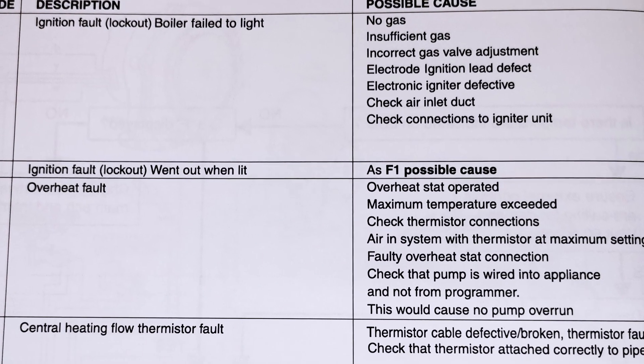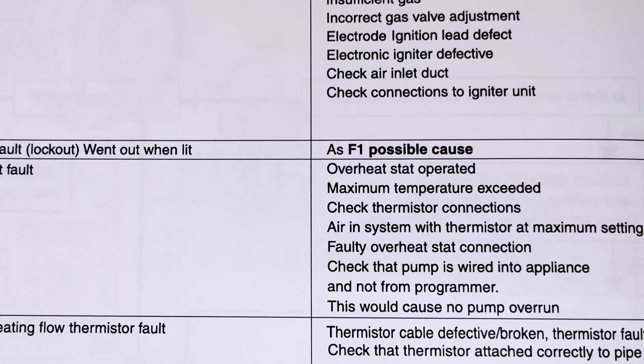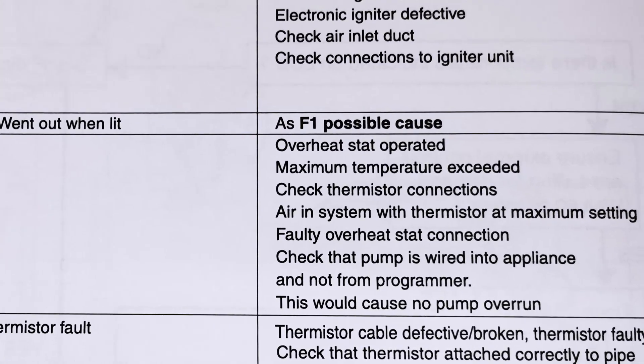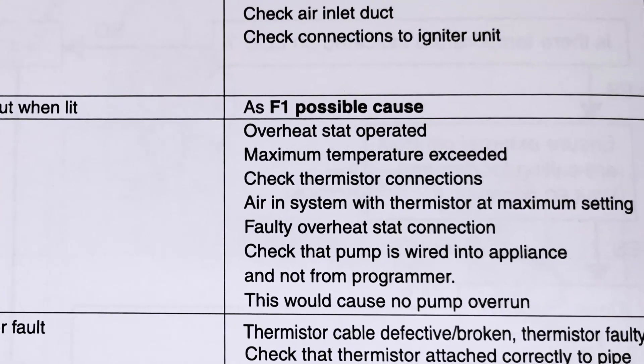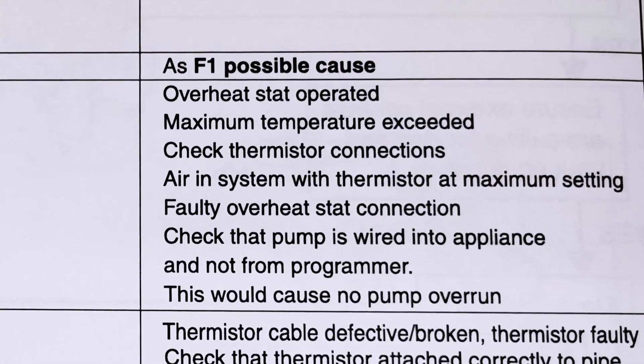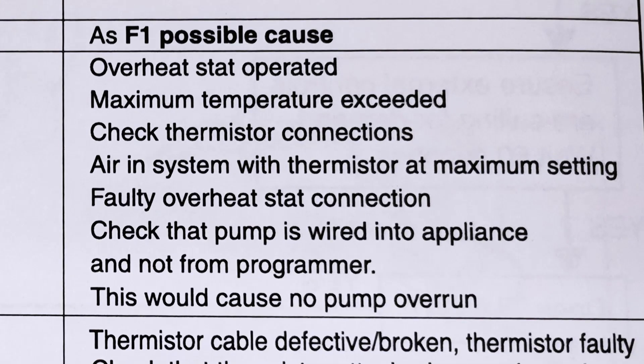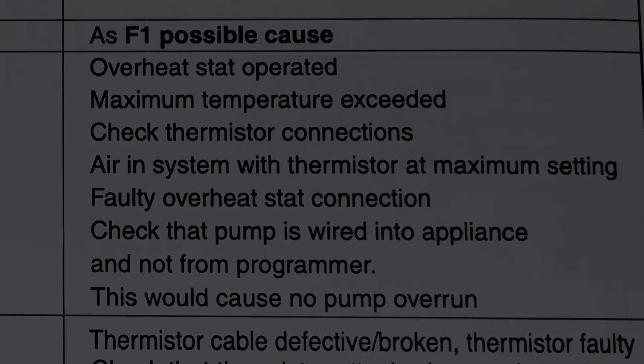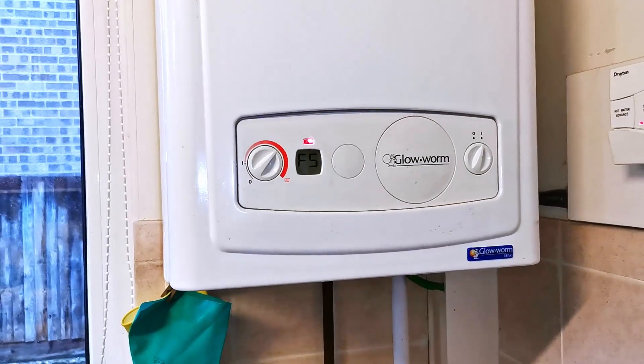Looking in the manual, the F5 is confirmed as an overheat fault. The possible causes listed are: overheat stat operated, maximum temperature exceeded, check thermistor connections, air in system with thermistor at maximum setting, faulty overheat stat connection, and check that the pump is wired into the appliance and not from the programmer — because that would cause no pump overrun. These are only guides pointing you in the direction of the fault.